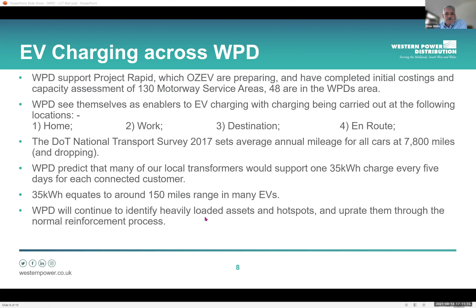One of the prerequisites whenever any LCT device is connected is for the installer to notify the host DNO, and that's one of the things that has fallen by the wayside. It's quite critical because it allows the DNO to work out if clusters are forming, especially in older suburbs or estates, because they weren't designed to the level we design them now.